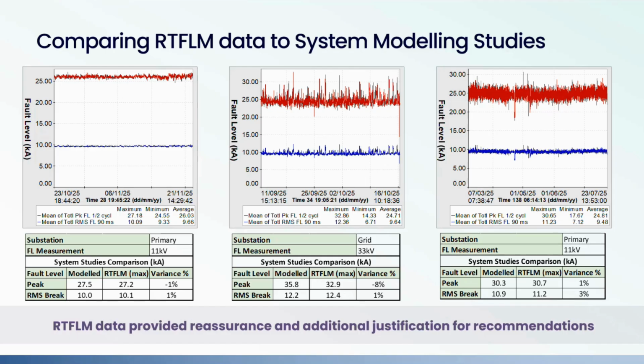So the substation on the left is a primary substation. It's a relatively new substation, so the fault level is quite consistent. There's not a huge amount connected at that location of the network at the moment. So the board is about half full, and you can see there's a very close correlation between the maximum fault level that's being measured during that period and what the models were telling us to expect. So there's a variance of -1 and +1 for peak and RMS break fault levels.